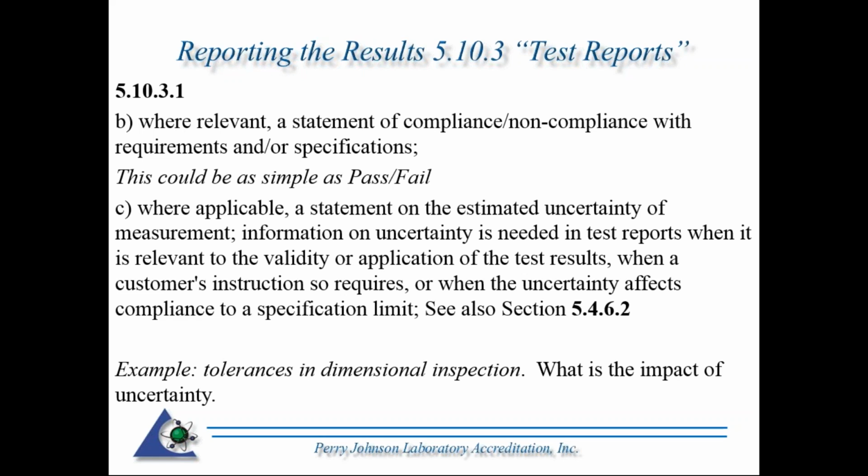Where applicable, a statement on the estimated uncertainty of measurement. Information on uncertainty is needed in test report when it is, again, relevant to the validity or application of the test results, when a customer's instruction so requires, or when uncertainty affects compliance to a specification limits. I referenced 5.4.6.2. This is the actual section of the standard on test methods, and 5.4.6.2 actually addresses uncertainty and testing uncertainty and when it needs to be determined.